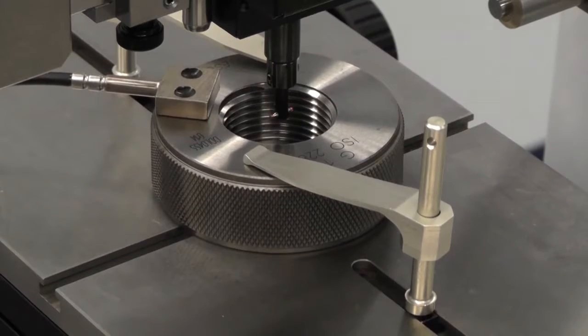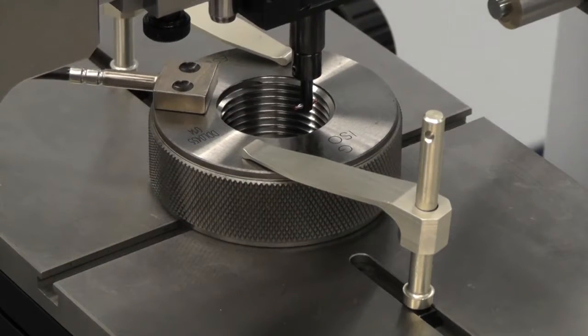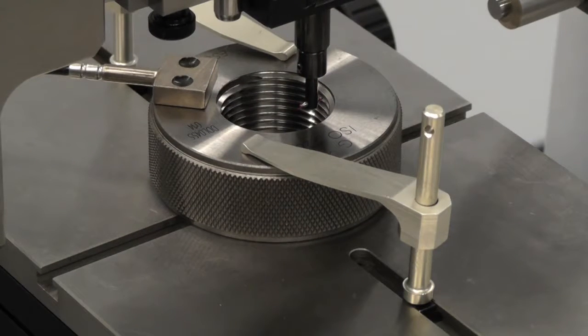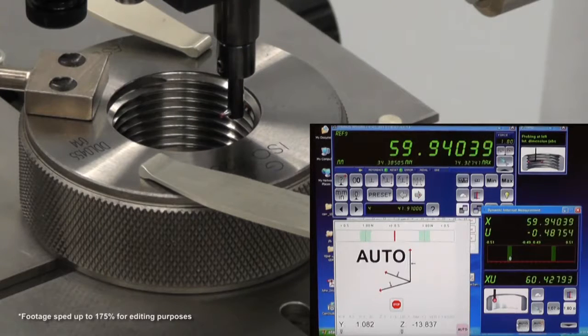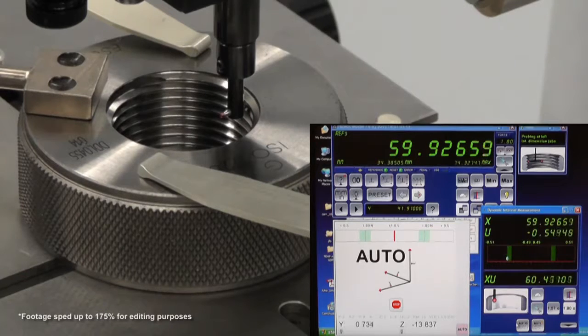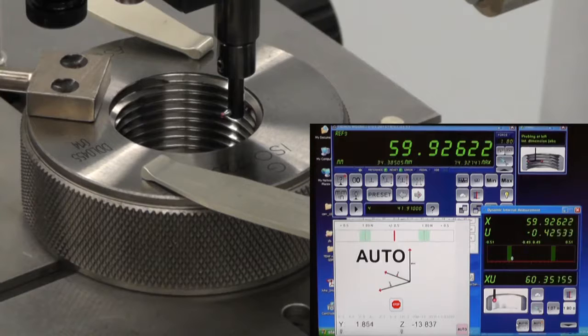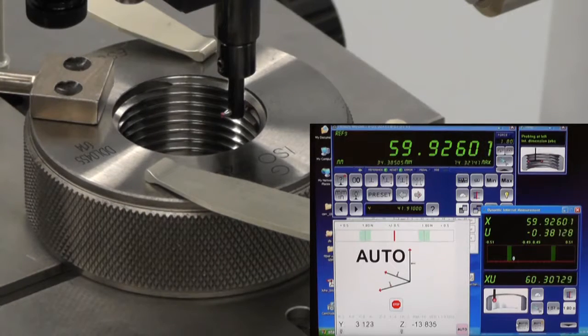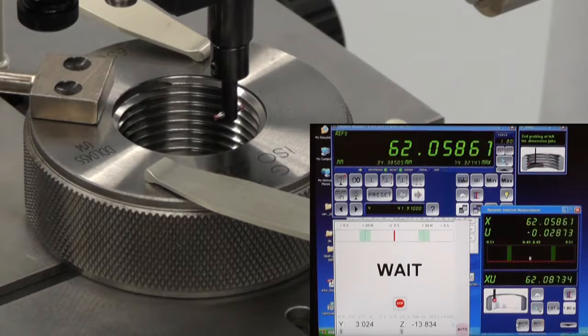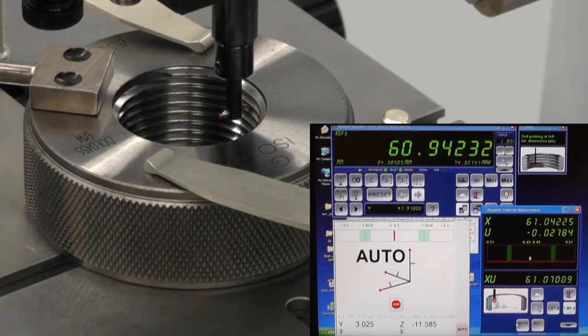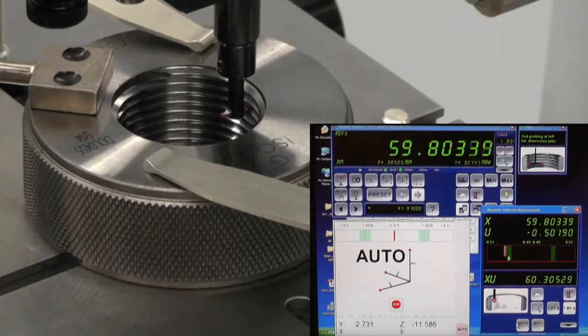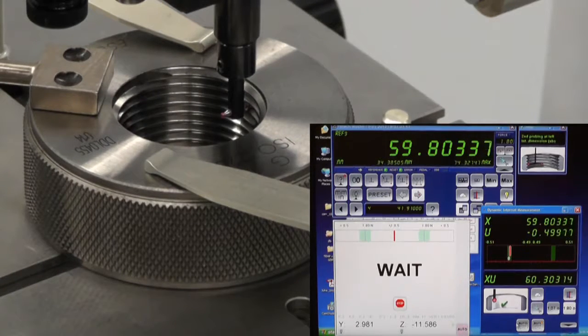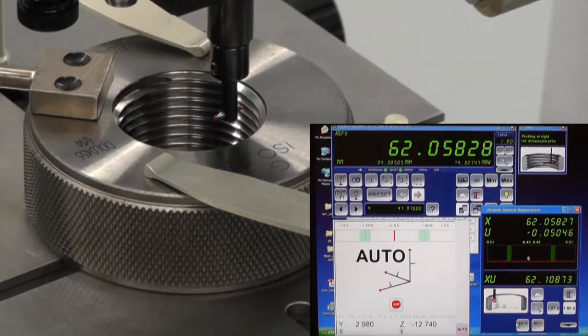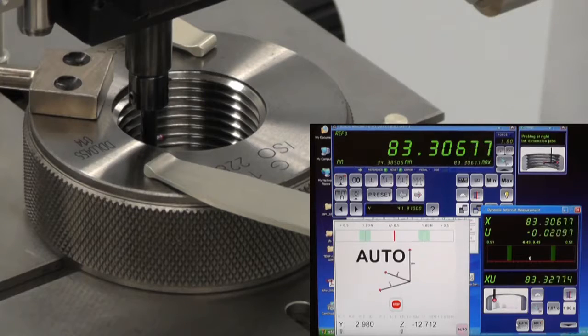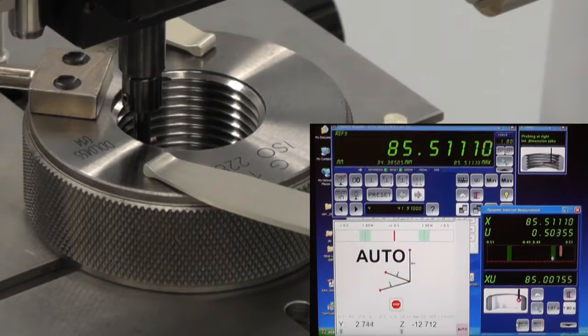With the thread dimensions programmed and the correct probe selected, the operator simply positions the probe in the first thread to be measured. From there, the probe will sweep for a reversal point, then repeat the motion on the next thread down. To complete the measurement, this action is then performed on the opposing ring wall. This 3-point method can be used on straight or tapered thread rings.